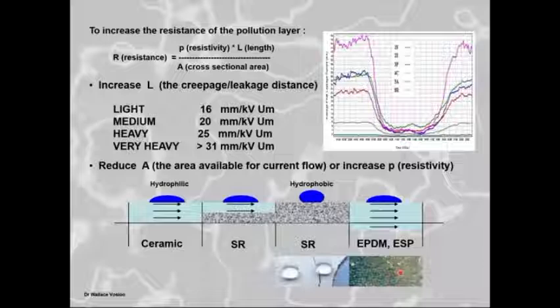tertiary, there's a weak spot in the actual structure of the polymer, and they always crack. You can take an EPDM or an ESP and they will start to form a white powder on them. And when you start looking at them with a magnifying glass, you find they crack. So now what happens is the pollution goes into the surface of the material, and now you've got a larger area available for current flow than with ceramic, and they perform worse than the ceramics.